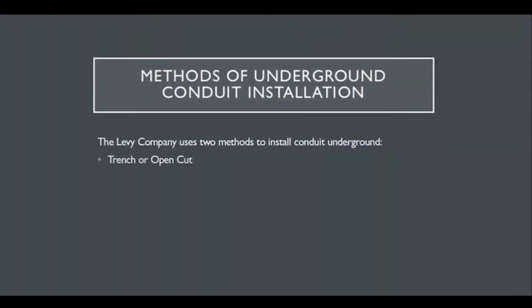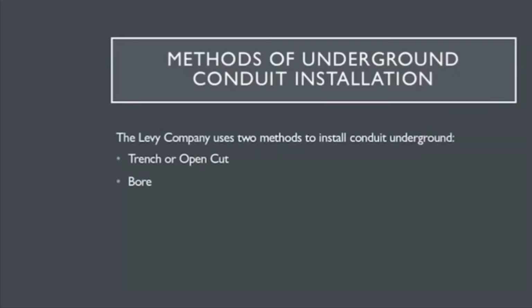We can go by trench or open cut, where employees use a machine such as a backhoe, excavator, or a trencher to dig into the ground to the required depth and install the conduit run. Or we can use the bore, which is the use of a bore machine to install a conduit. The bore method is normally used in a previously developed area that cannot be disturbed. An example of this is installing conduit under an existing road that is in use. Through boring, we can get underneath that road without damaging it at all.